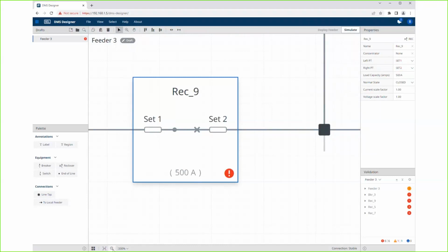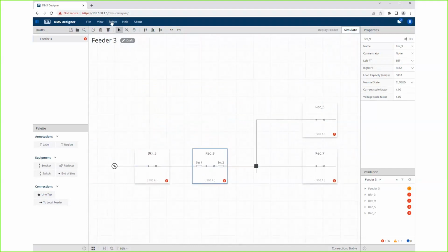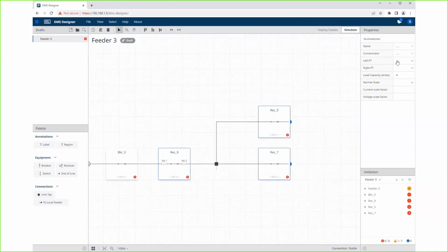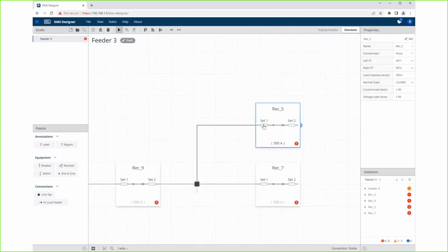That was a big objective of ours. There is no save button, and there's continuous validation. It should tell you immediately if there's a setting that doesn't make sense, either for FLISR or for the physical world as a whole. You can't have a voltage measurement measuring 2 points on each side of the switch. Okay, so now I've quickly set up PT locations on each side of these switches. I'm just showing you several different ways to do it here. You can either interact directly with the device, or there are several ways to do it. And now I'm adding a connection to an adjacent circuit, another feeder. You can call these whatever you want. You will develop a routine that makes sense for you or for your organization. I like to name them after the device they're closest to.